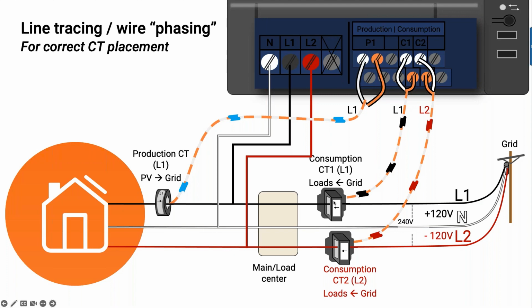That's why we actually have a voltage measurement for line 1 and a voltage measurement for line 2. And that's actually off of the main power lugs that feed the IQ gateway. That's how we measure voltage for each phase: voltage for line 1, my black line, and voltage for line 2, my red line. That's my voltage measurement. My current measurement is through the CTs.